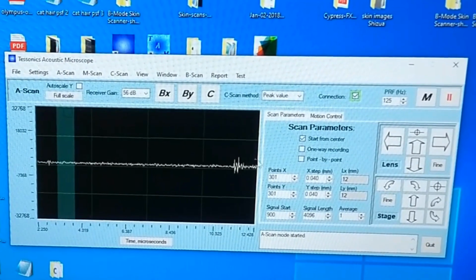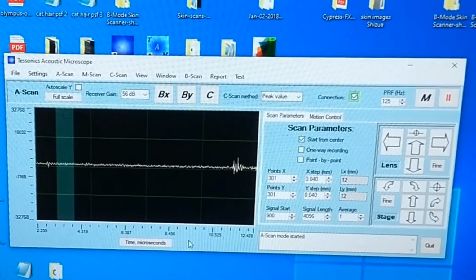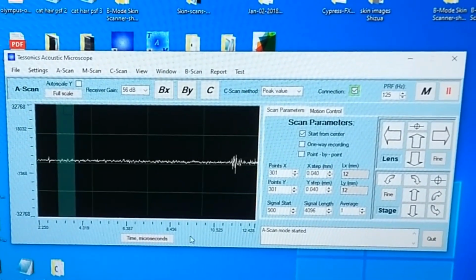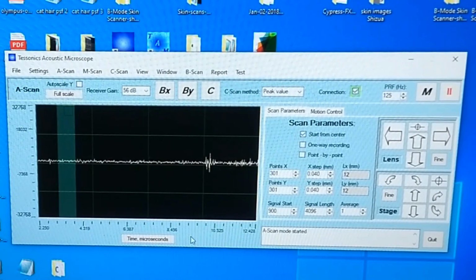The wave on the right is a signal reflection from the sample. As the transducer is lowered closer to the sample, the reflection will move to the left on the timescale, as it has a shorter distance to travel before hitting the sample and causing a reflection. As the focal point of the transducer comes closer to the sample, the amplitude of the signal will increase.